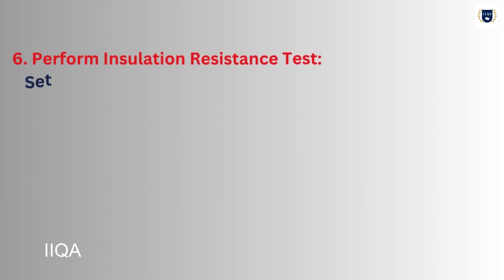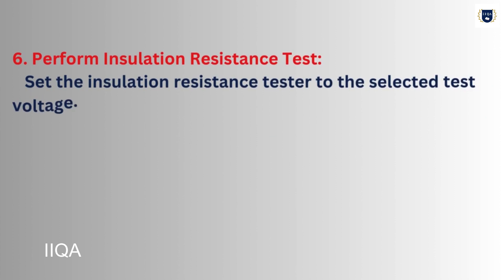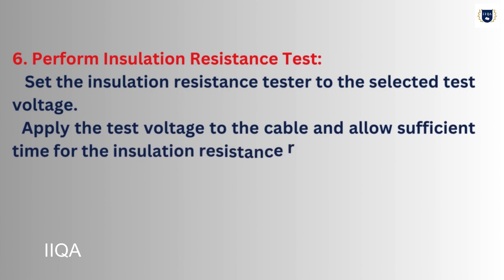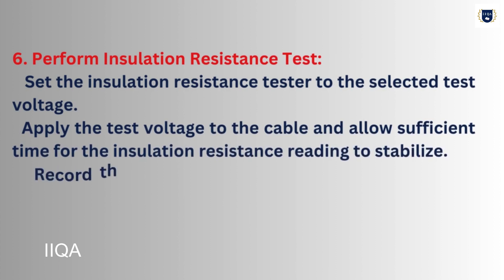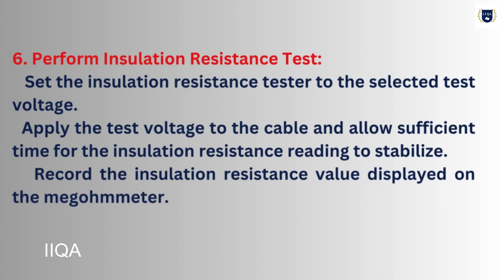Step 6 - Perform Insulation Resistance Test: Set the insulation resistance tester to the selected test voltage. Apply the test voltage to the cable and allow sufficient time for the insulation resistance reading to stabilize. Record the insulation resistance value displayed on the megohmmeter.